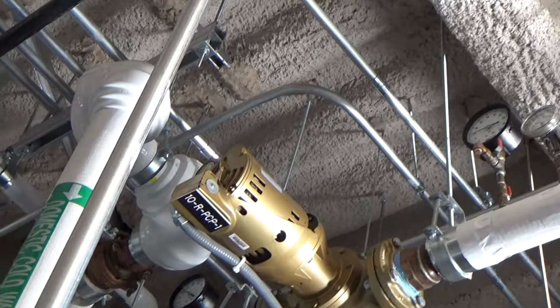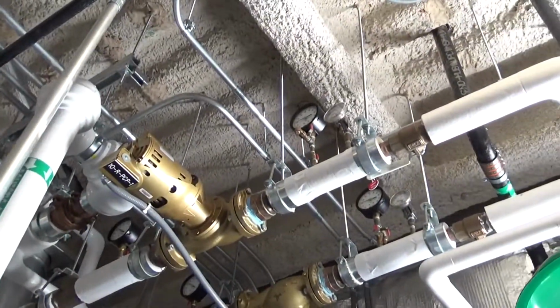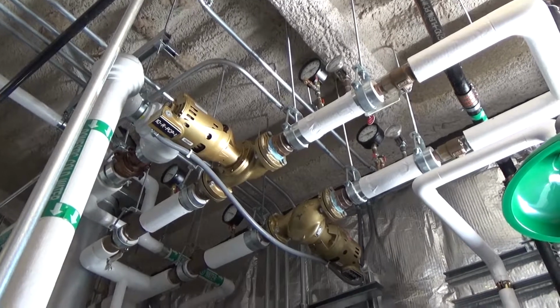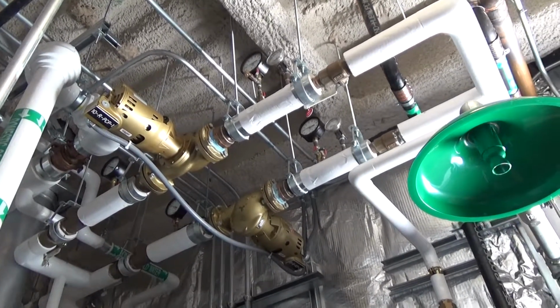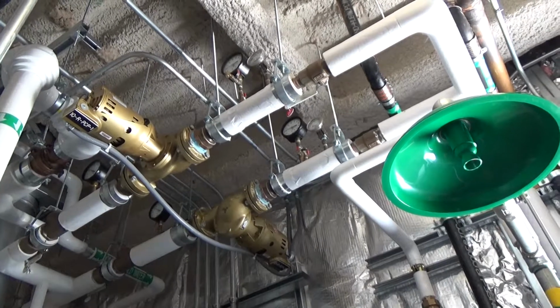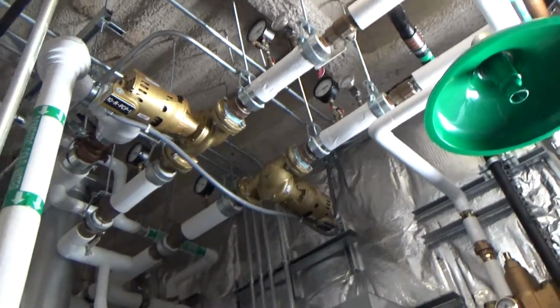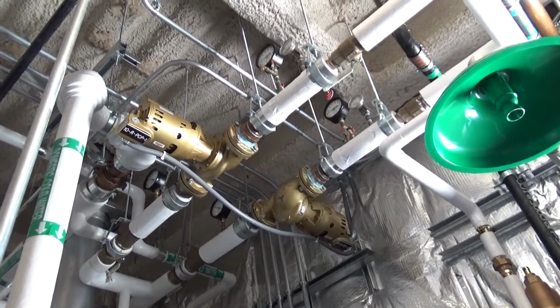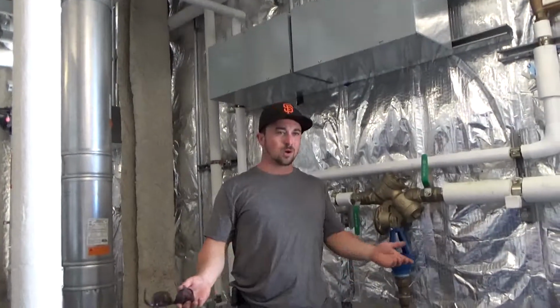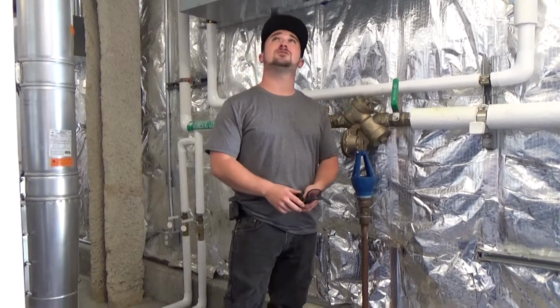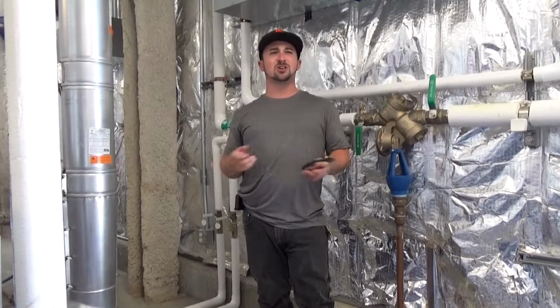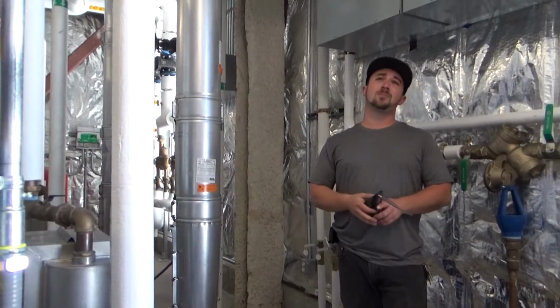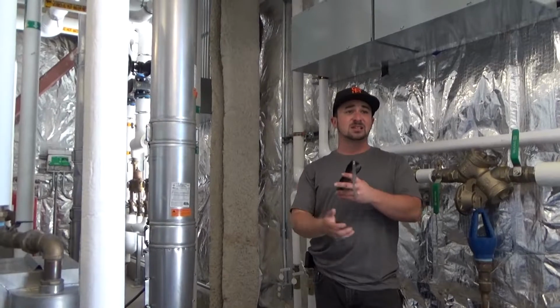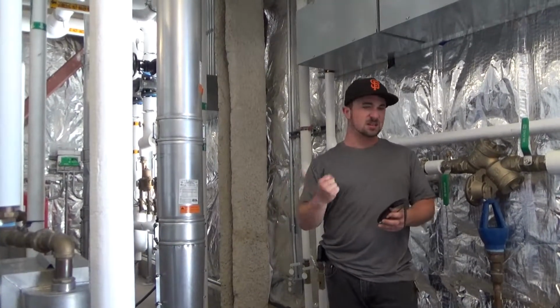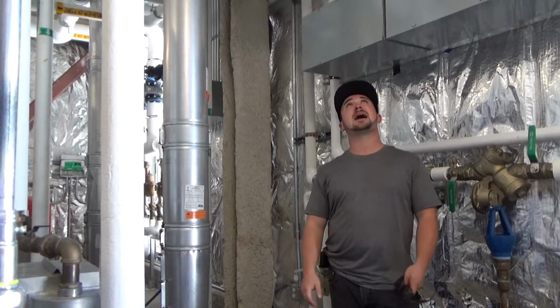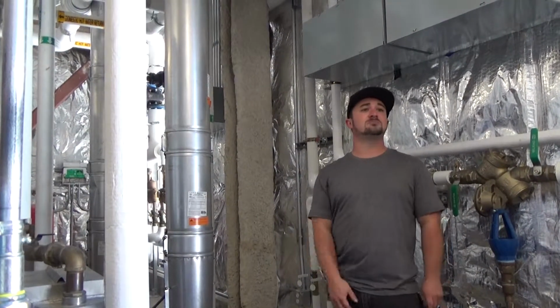You have your conduit connections or electrical connections on the end, right where the tag plate is. If you guys ever had to do any rewiring or anything like that, you would just take off that little back cover, and that's pretty much it. It would be a good idea to blow them out every once in a while. That's what I was going to say next. It's domestic water and the water's pretty clean out here. But every few years, if you start having issues with flow and pressure and the water's not moving quickly enough, you might want to pull that thing apart and verify that everything's clean in there. Maybe clean it out, take a screwdriver, scrape off any debris or calcium, reinstall, and it should be good.